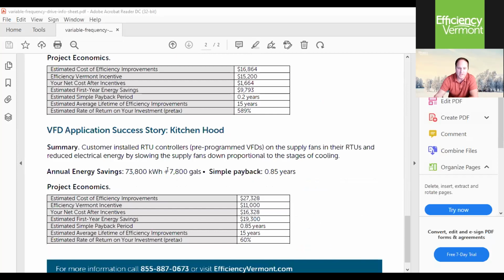If you're over exhausting conditioned space, you're throwing away heating and or cooling energy excessively. If you need that level of exhaust, then you need it. But if you don't, and the exhaust fan speed can be modulated down and still provide the required exhaust, you will get not only fan energy savings, you'll get heating and or cooling savings. So again, this form is on our website. If anybody wants it, we can send it to you following the webinar.